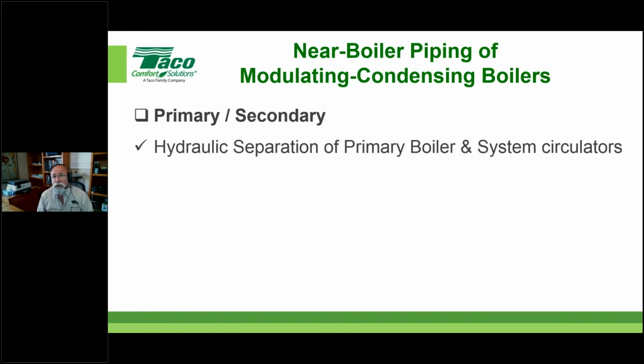Well, primary secondary when we're talking about boiler piping has to do with the separation of the circulators within the system. Now, the one that's on the boiler should only be affected by anything that's in the circuitry of the boiler. That means the heat exchanger, the near boiler piping, the closely spaced T's, the hydraulic separator, etc. Okay, that should be its only worry. And then the system circulator or zone circulators that are on the secondary side, those should only be affected by what they're responsible for. So it's actually just separating the lines of responsibility and making sure that circulator is only doing what it needs to do.